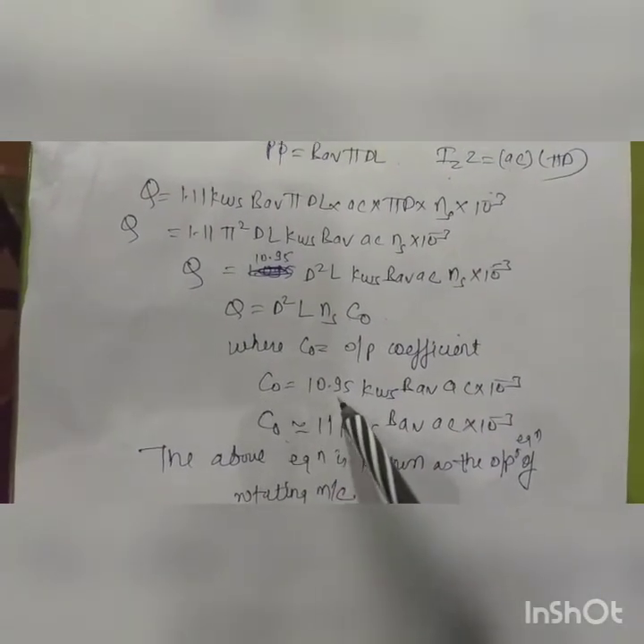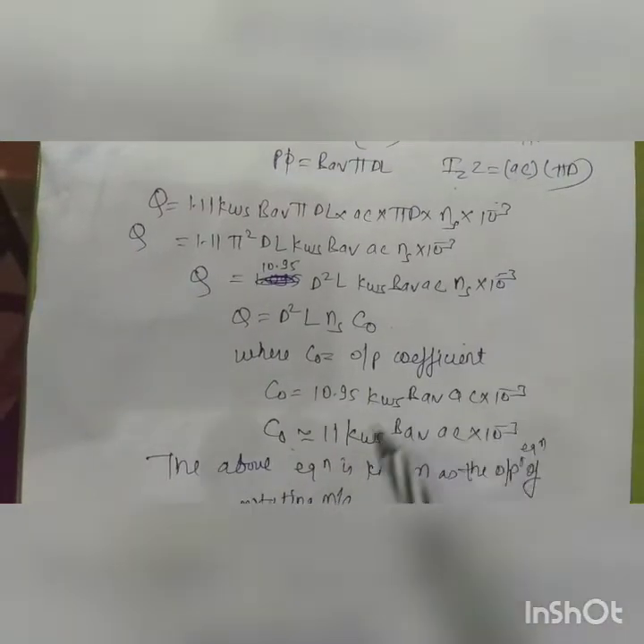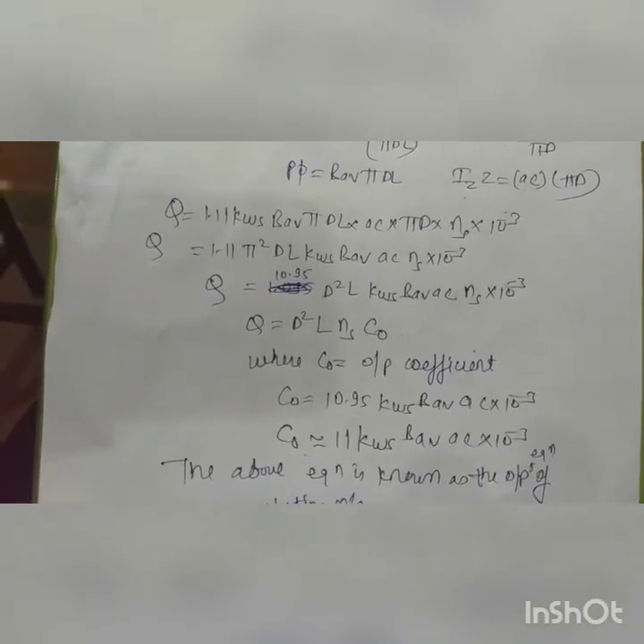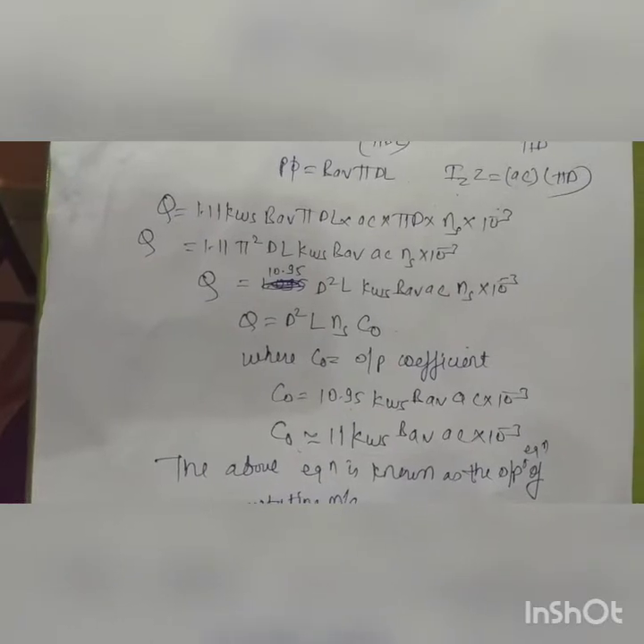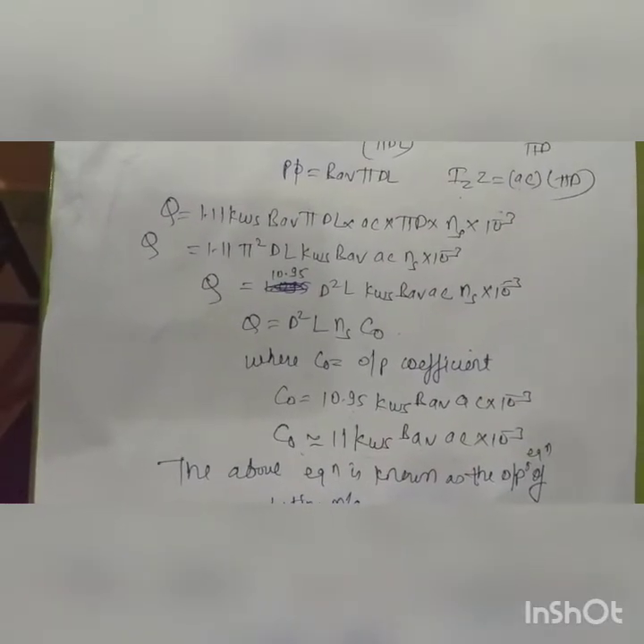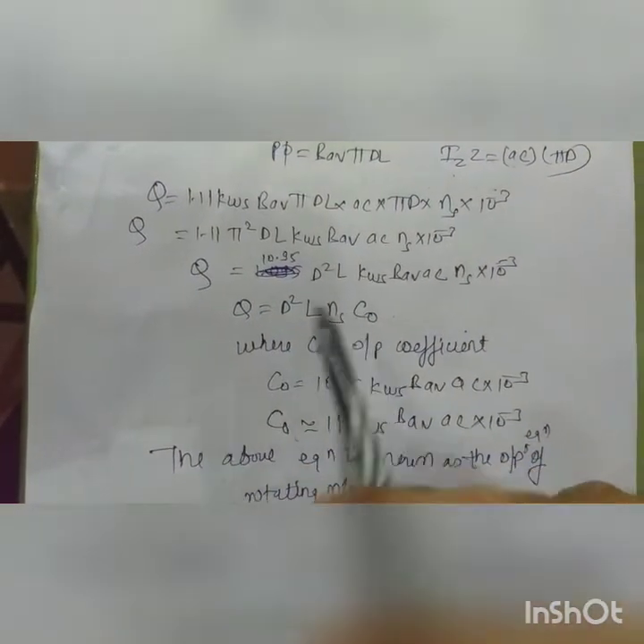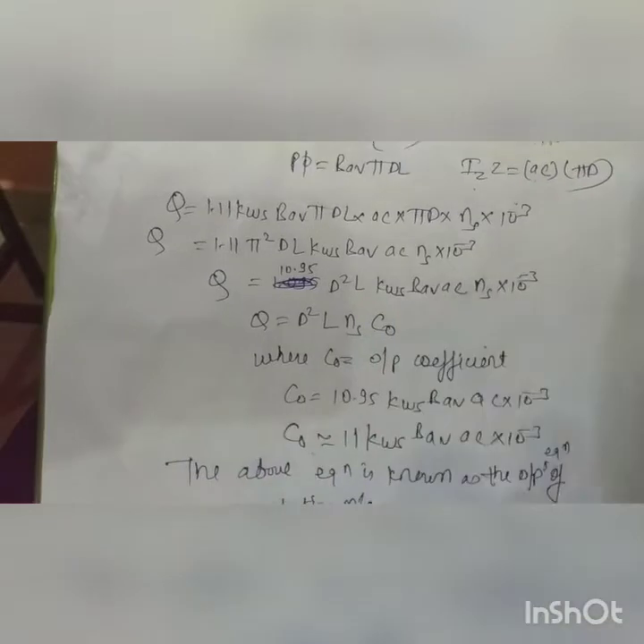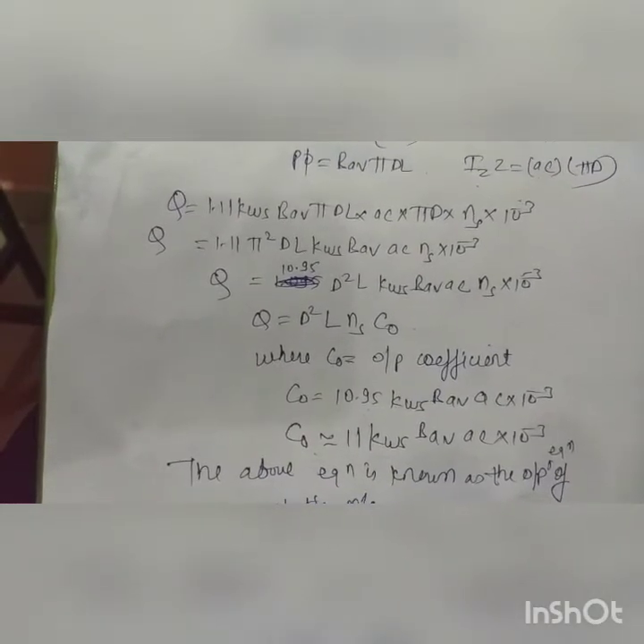The output coefficient C0 equals 11 times the stator winding factor, multiplied by average flux density (Bav) and average current density (ac), times 10⁻³. The stator winding factor is nearly constant, ranging from 0.96 to 0.98, so the output coefficient essentially depends on the average flux density and average current density. Since D is diameter and L is length, D²L represents the volume of the active part, which is responsible for power generation.